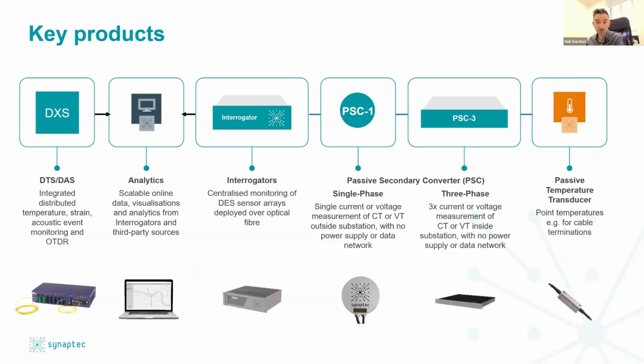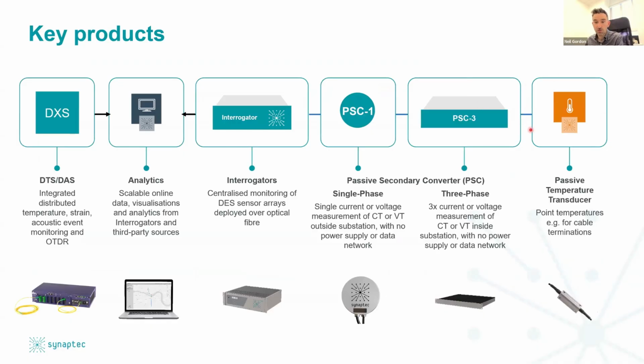So what are those key building blocks? Well, they're all listed here. There's quite a lot here, so let me just get this laser pointer so you can see what I'm talking about. On the right-hand side here, you've really got the DES sensors. Starting from the right, you've got our passive temperature transducer, which is a small point temperature sensor often deployed to measure temperatures on assets like cable joints and terminations, or any other critical items of plant. This example here is about 2 or 3 centimeters long. It's a small patch that gets applied to any item of plant that you want to measure the temperature of.